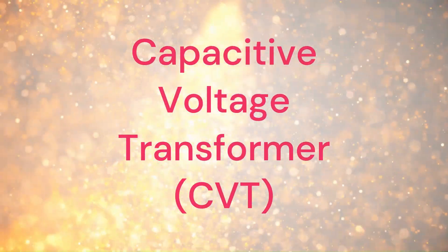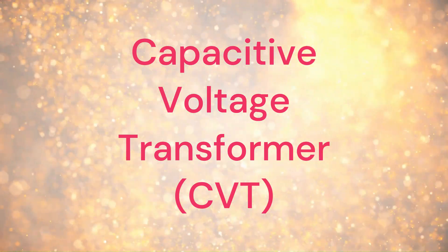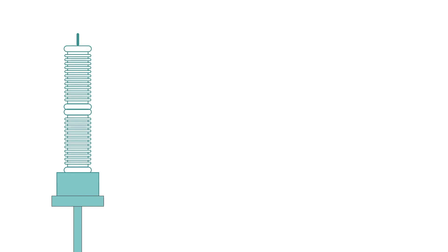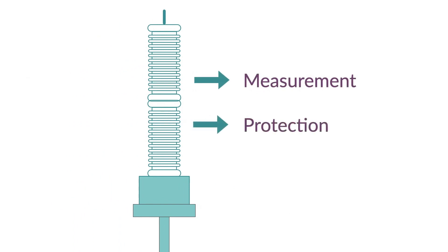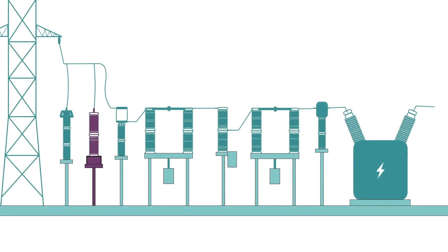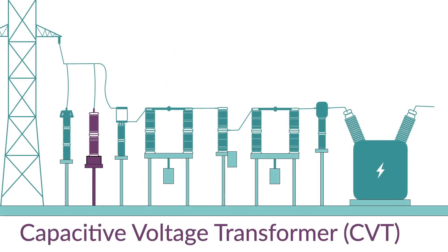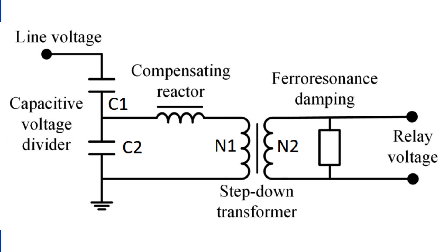Now, let's explore capacitive voltage transformers, or CVTs. CVTs are designed for precise voltage measurements, particularly in high-voltage transmission systems. They are essential for metering, monitoring, and protection in electrical systems. These transformers utilize a capacitive divider network to step down high voltages while maintaining accurate voltage ratios. As you can see in the diagram, it is a combination of a capacitive voltage divider, an inductive element, and an auxiliary transformer. The capacitor or potential divider is placed across the line whose voltage is to be measured or controlled.